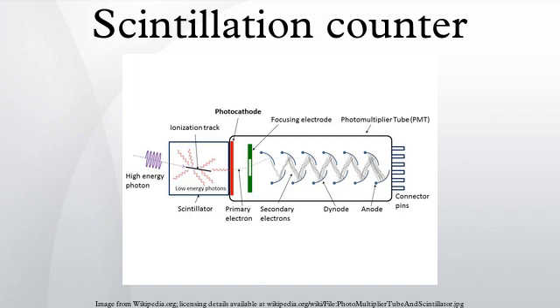It consists of a scintillator which generates photons in response to incident radiation, a sensitive photomultiplier tube which converts the light to an electrical signal, and electronics to process this signal.